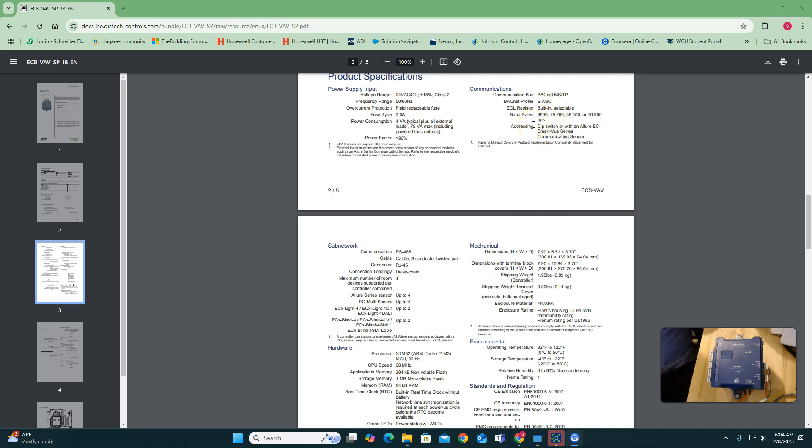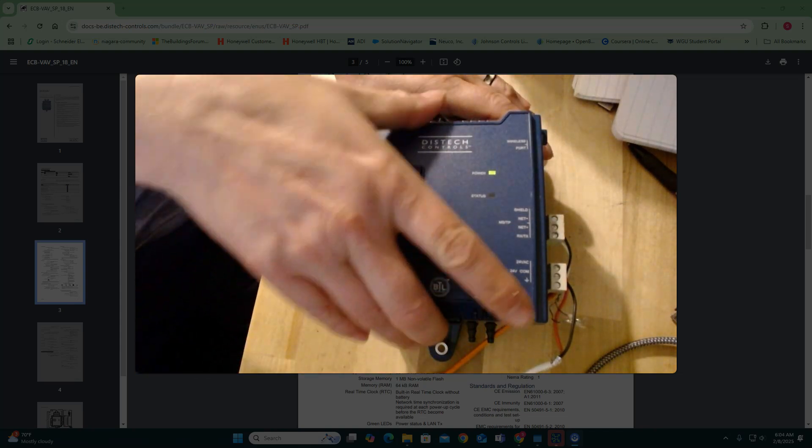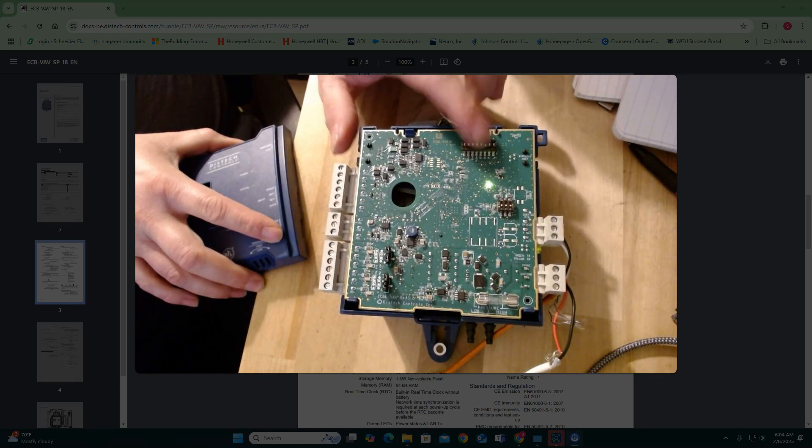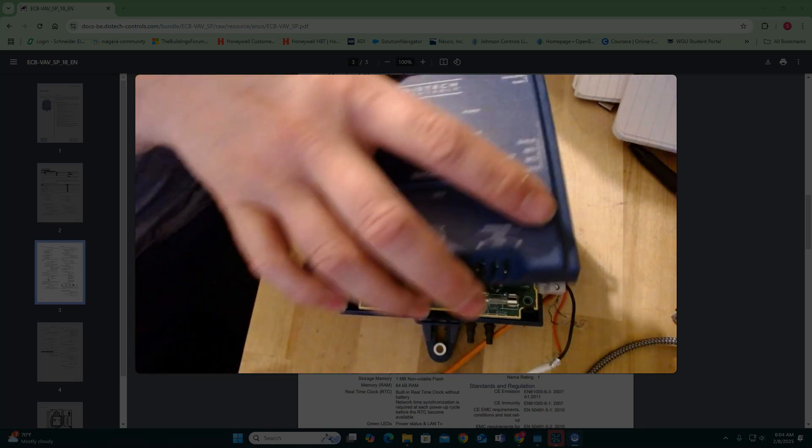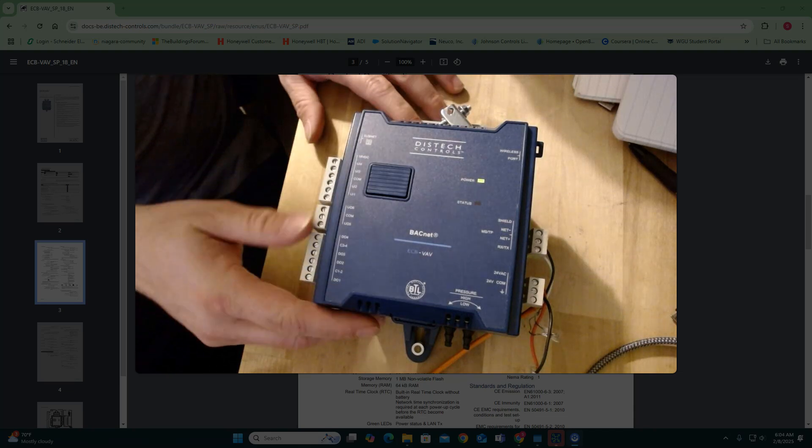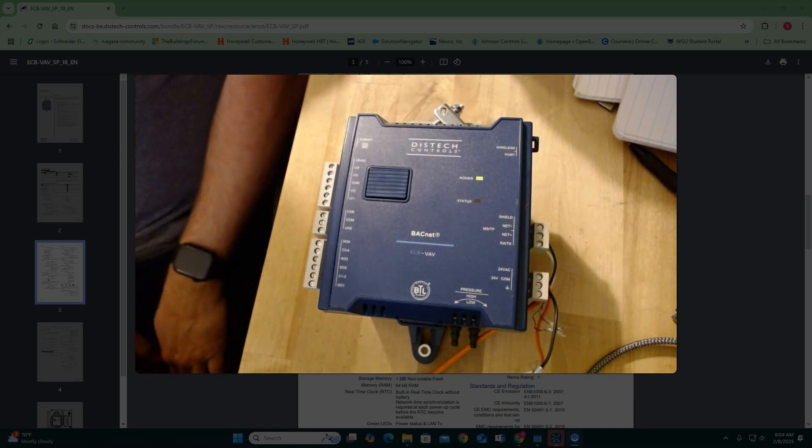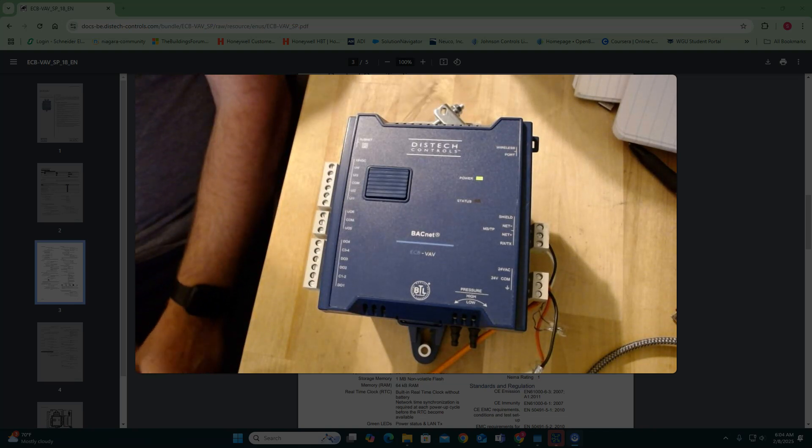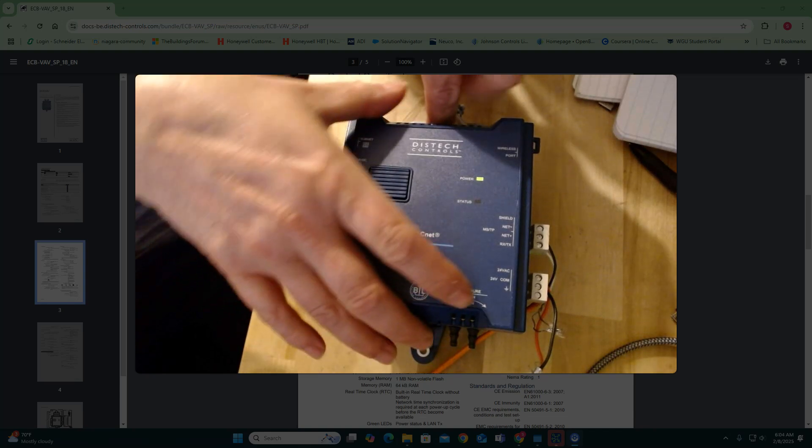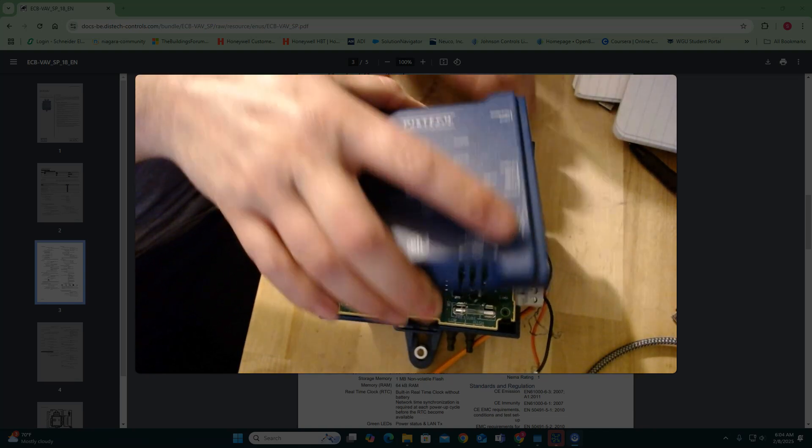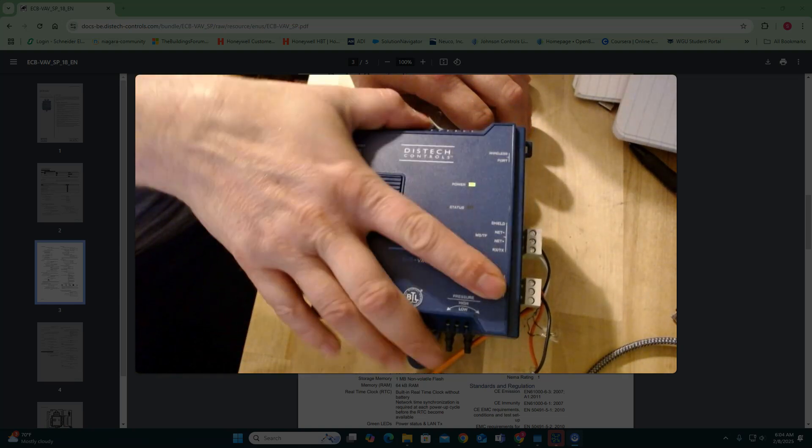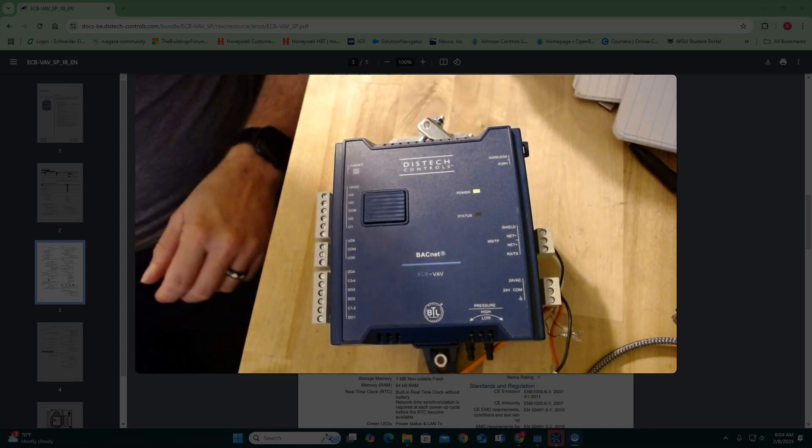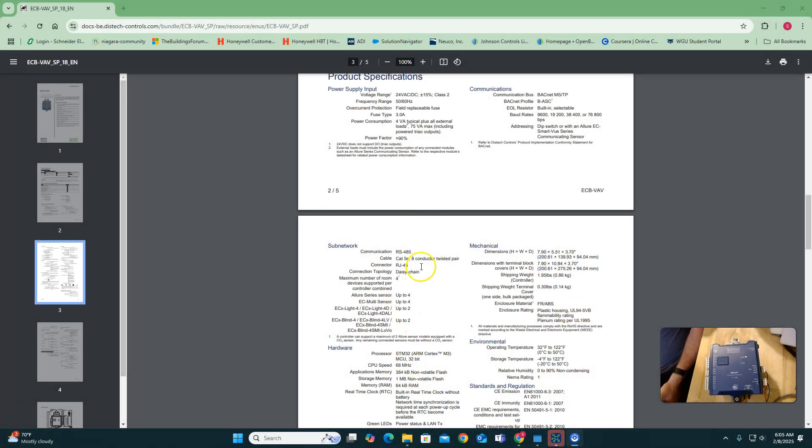Baud rates, it can go all the way down to 9,600, all the way up to 76,800. Dip switching, which I don't really like. You do have to take the cover off to address it. You got binary addressing up here, which is fine. But you do have to remove the cover to address it. And if you're like me, that has the mind of a goldfish that forgets all the time, you forget to address it, you go install it in the VAV. And then you have this damper sticking out right here. And sometimes it's hard to get the cover off. So I don't like that you have to take the cover off to address it, but I get over it.